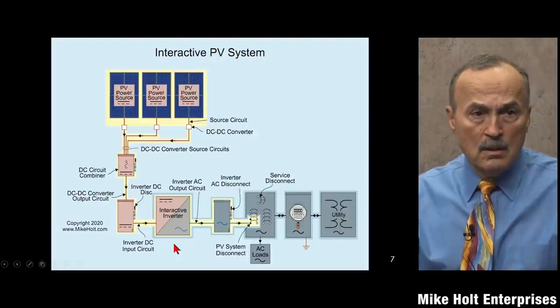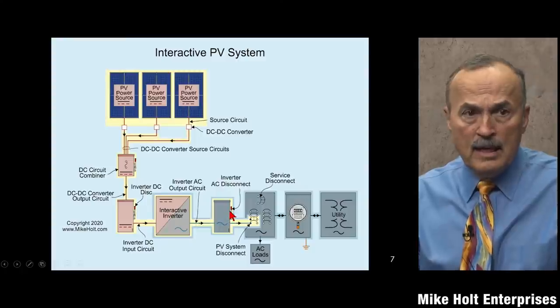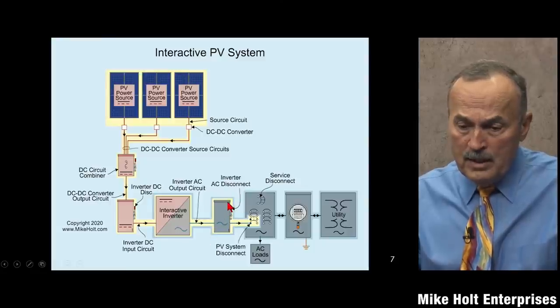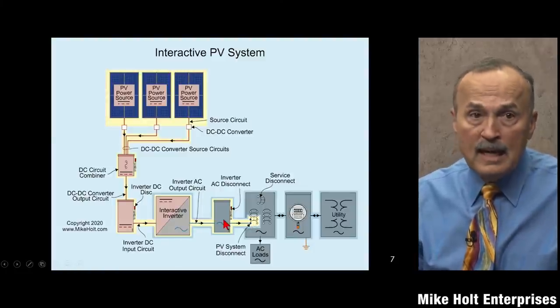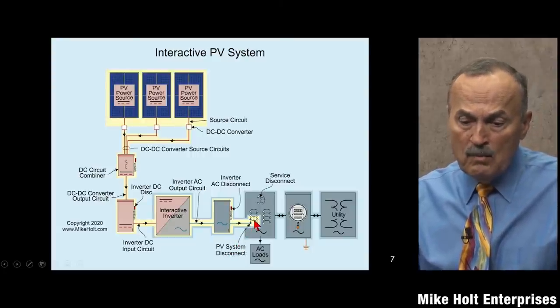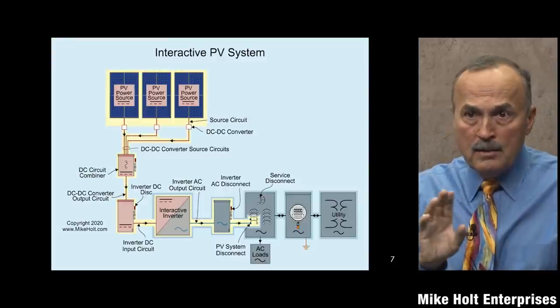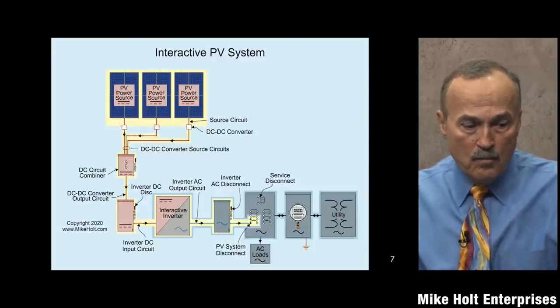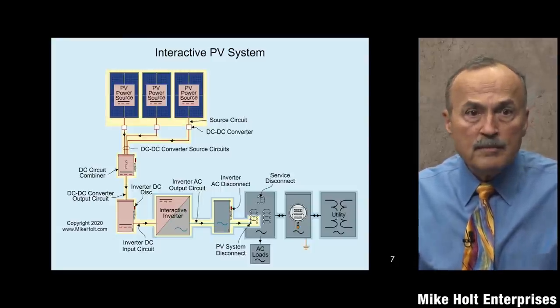The AC inverter disconnect can also be incorporated within the inverter itself, so you don't need a separate disconnect for AC and DC. Or the back-feed circuit breaker could be your AC disconnect - we don't even have to have a separate disconnect if the back-feed circuit breaker meets the requirements for equipment disconnect. That's where the PV system ends, so it's a matter of where you locate things and following the code rules.